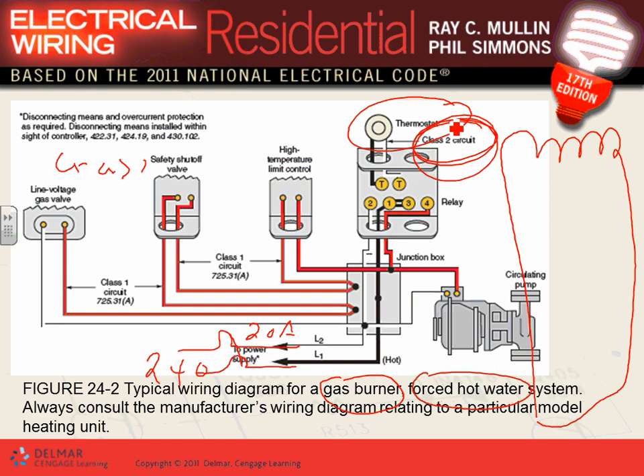The Class 2 circuit is a power-limited circuit. They are typically 30 volts or less and very limited in power—100 volt-amps maximum. The thermostat wire is what we call a Class 2 cable. You shall not put that thermostat wire inside a pipe or cable that also carries power—you must separate the power from the control circuit. There are also safety circuits: Class 1 and Class 2.